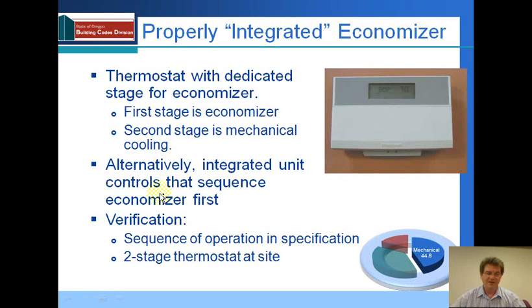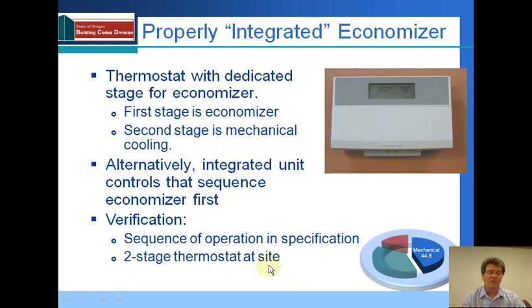Where can you find this out? You can verify it in the sequence of operation or commissioning report, or you can verify it by noticing that there's a two-stage thermostat at the site.